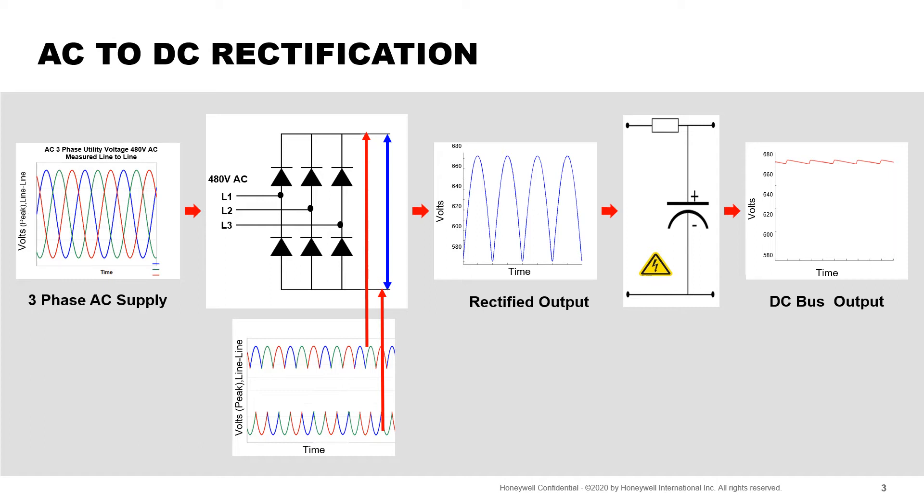The DC with these ripples then passes to the DC bus portion, where capacitors absorb the AC ripple and deliver much smoother DC power. One important thing to mention in regards to these capacitors is safety. The function of a capacitor is to store energy. This is necessary for the VFD, but it's also a source of danger. When power is disconnected from the VFD, the capacitors remain charged for at least five minutes. For safety's sake, after disconnecting power, wait until the display goes blank. Then wait five minutes to be sure the capacitors are fully discharged.